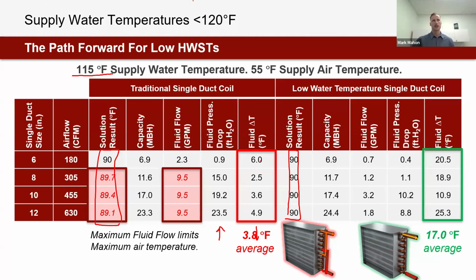So this comparison here is more of the traditional single duct 2-row to a low water temperature 2-row. But this is kind of the paradigm that I envision a lot of design engineers are seeing. We schedule 2-row single duct hot water coils. We have an aggressive hot water supply temperature, and it simply just doesn't work. So I'll pause there for some questions because we have another transition here.